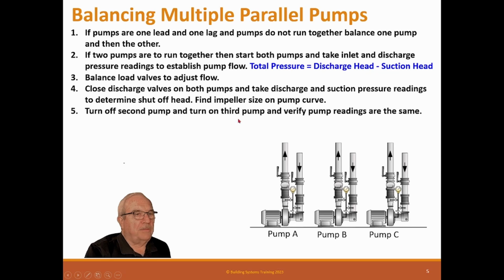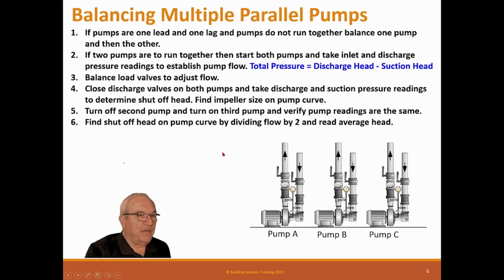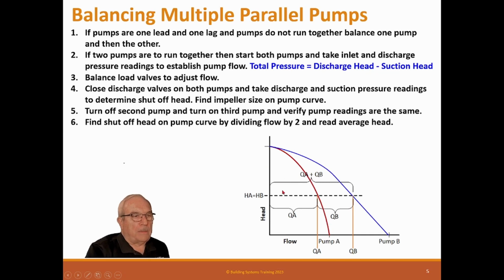Turn off the second pump and turn on the third pump to verify the pump reading. So once you've got these two balanced, turn one off and make this the second pump and make sure you're still the same: that when these two are running, you have the same pressures as when you have these two running. Find the shutoff head of the pump curve by dividing flow by 2 and reading the average head. The pressures are fine. You don't need to do that. But here's the curve to show what I'm talking about.